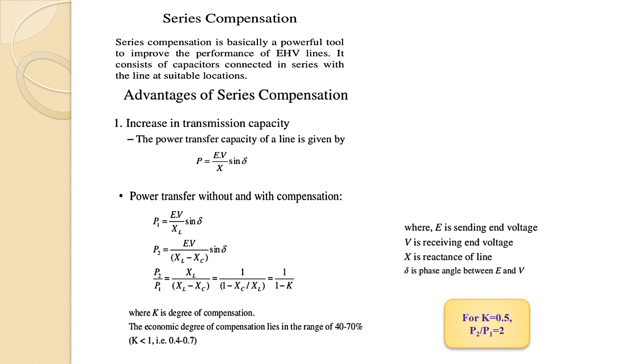Now suppose K is equal to 0.5. If you calculate the ratio P2 by P1, it comes out to be 2, meaning that the power transfer is doubled by 50% compensation. Another advantage of series capacitor compensation in the line is the improvement of the system stability. We can see that for the same amount of power transfer and same values of E and V, the delta in case of a series compensated line is less than that of the uncompensated line.